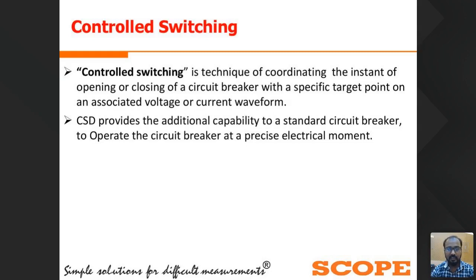The electrical point we are targeting for the operation of the circuit breaker depends on the type of application. For the reactor application, we are using different target angles. For the power transformer application, we are using different target angles. Same for the capacitor bank and transmission line applications, the electrical target point is different. So by using the control switching device, we are trying to operate the circuit breaker at the precise electrical moment. If we switch the circuit breaker at that moment, the transients and switching surges will be minimum.